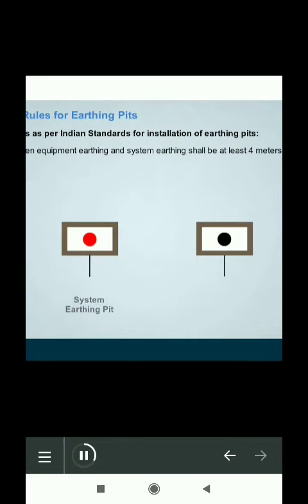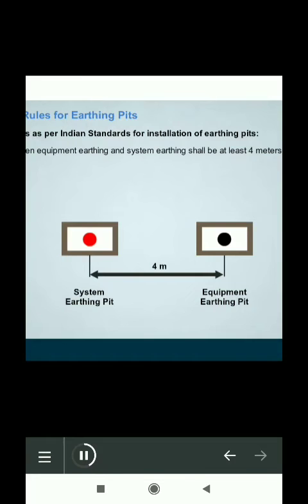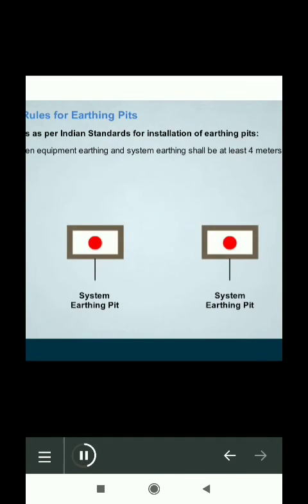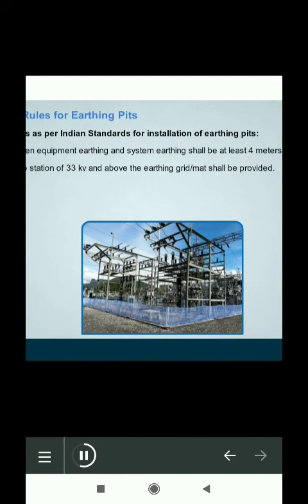Distance between equipment earthing pit and system earthing pit shall be at least 4 meters. As you can see here, this image shows two different earthing pits. Red one being a system earthing pit and the black one an equipment earthing pit. If different pits are required in the same location, then they should be installed 4 meters apart from each other. Similarly, the distance between two similar pits, for example, two equipment earthing pits or two system earthing pits, should be 2 meters.